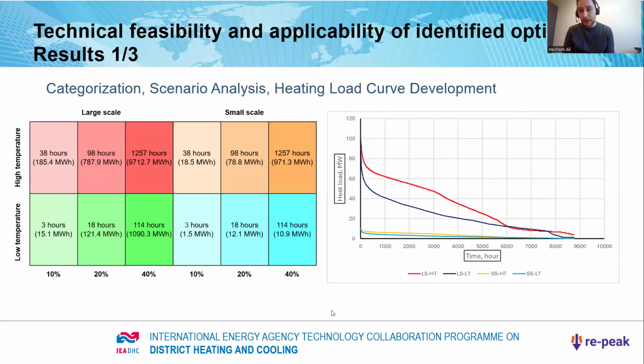We can see the main key takeaway from this curve: the low temperature, efficient network has a smoother curve, which means that with a low temperature district heating network, the peak load will occur much less at the different capacities. We can see it in numbers in the matrix on the left side. For example, for 10% in the high temperature network, the peak load will occur 38 hours a year, while in the low temperature network it will be 3 hours.